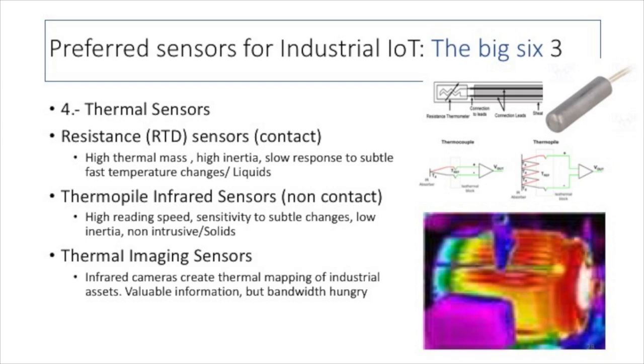Thermal sensors, okay. Thermal sensors are very important in industry. Controlling the temperature of the process or the temperature of the machinery is a very important physical variable to be acquired and analyzed. Resistance RTD sensors like the PT100 have been used for many years to detect temperatures in industrial processes. This is the sensor you see on the upper right side of the slide. We hate them. They have high thermal mass, high inertia, very slow response to subtle fast temperature changes. We only use RTD sensors to control temperature in liquids.